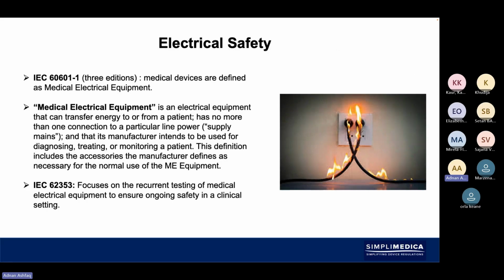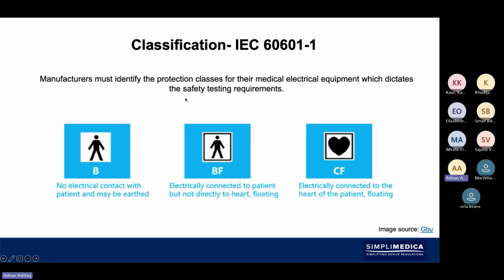If you've got a device which is run by electrical requirements or battery, then you also need to look at the electrical safety. IEC 60601-1. There are many subsets of this which you need to have a look at. Things like EMC testing, also ingress IP rating, and a number of other tests that you need to have a look at for medical electrical safety. So that's another thing to think about.